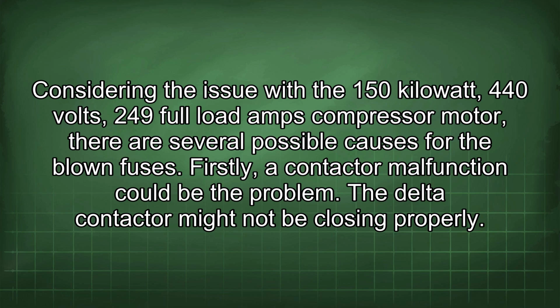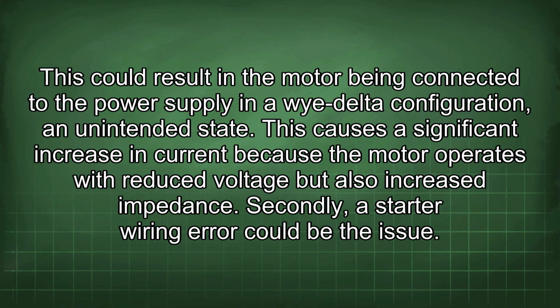Firstly, a contactor malfunction could be the problem. The delta contactor might not be closing properly. This could result in the motor being connected to the power supply in a Wye-Delta configuration, an unintended state. This causes a significant increase in current because the motor operates with reduced voltage but also increased impedance.